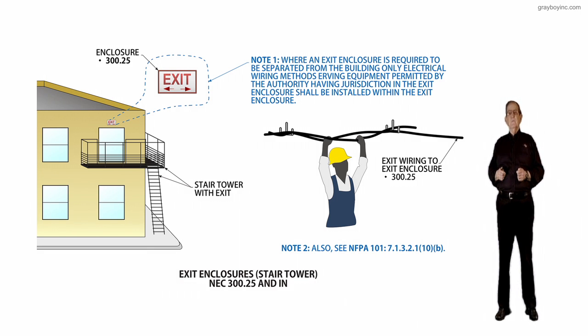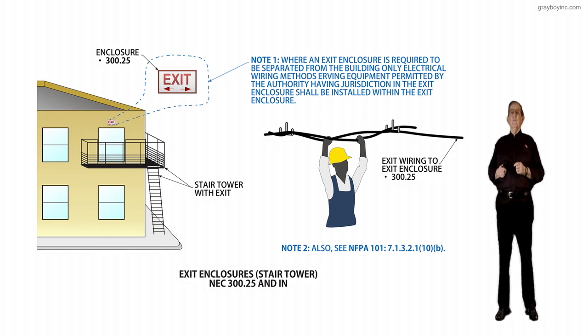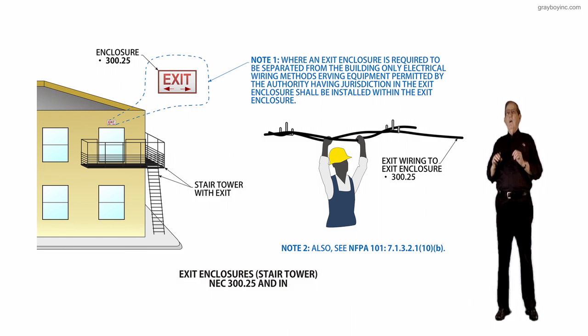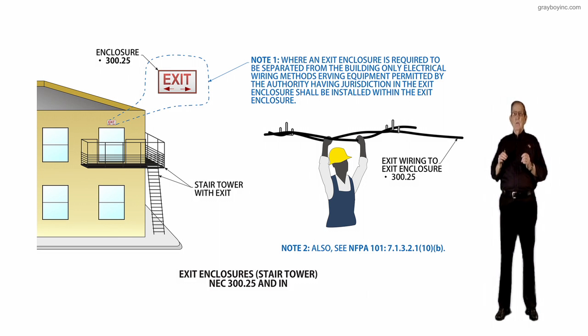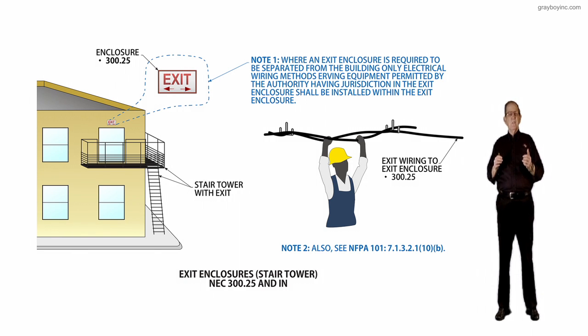Reviewing the fine print notes: notice the exit sign in the illustration titled 'exit enclosure' with a bullet referencing 300.25. Note one states that when an exit enclosure is required to be separated from the building, only electrical wiring methods serving equipment permitted by the authority having jurisdiction in the exit enclosure shall be installed within it. Note two advises reviewing NFPA 101, Section 7.1.3.2.1, item 10b, for more information beyond what is listed in the NEC.